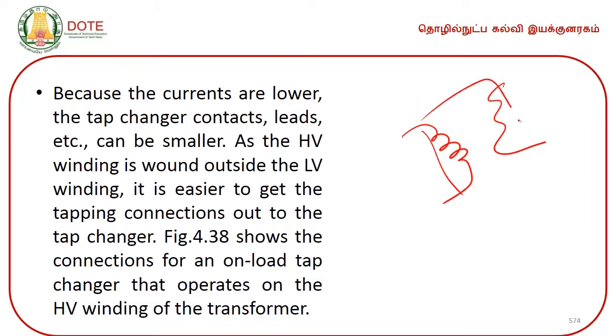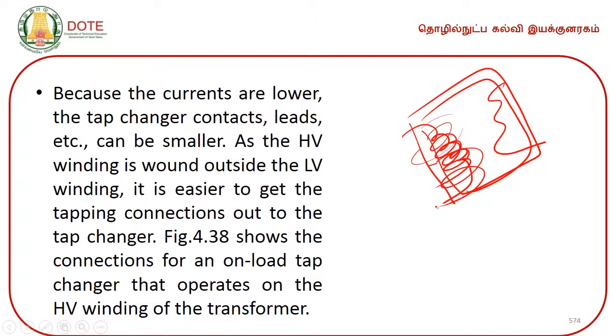If this is the core, normally the low voltage coils will be wound first, and on top of it, after the insulation, the high voltage coils will be wound. So, since all the tappings are taken from the HV, that is the high voltage winding, it is easy to access all the tappings. That is what it states.